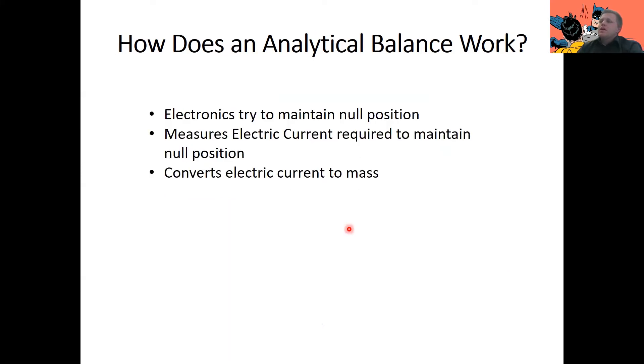So in summary, how does an analytical balance work? Well, it tries to maintain a null position. It does that by trying to balance the force applied by the sample with the force of your electromagnetic field. We try and have those equal but in opposite directions so they cancel out. So it then measures the electric current required to maintain the null position. And then converts the electric current to a mass using its internal calibration.